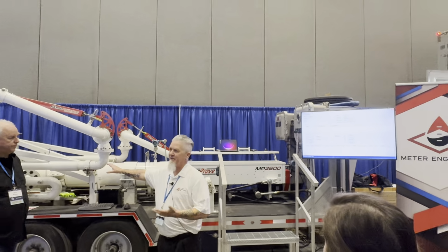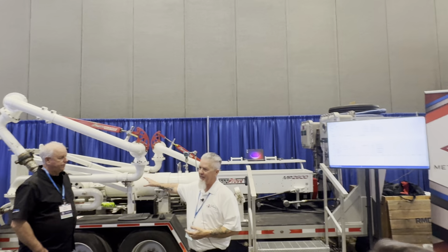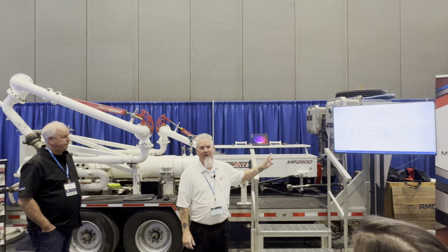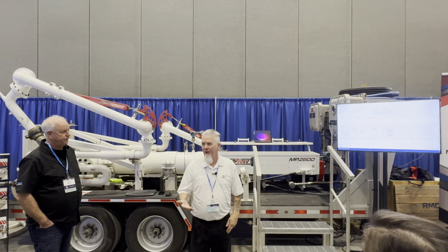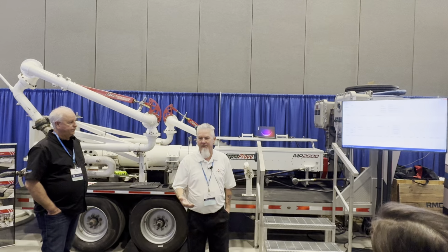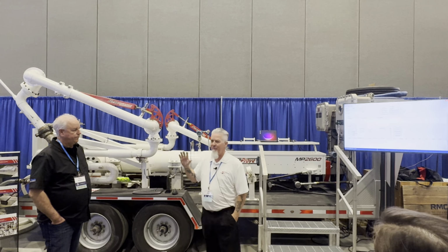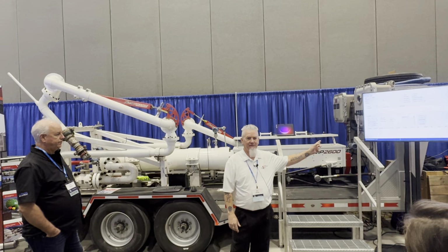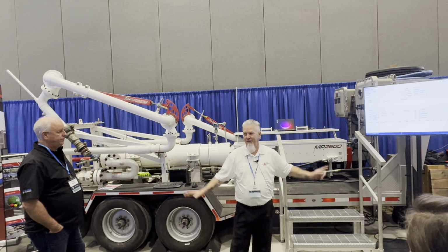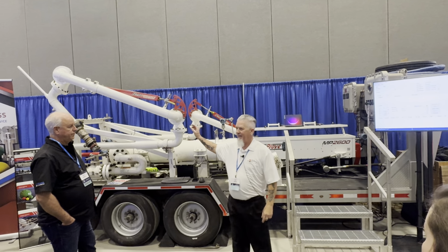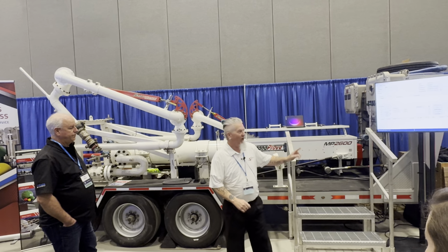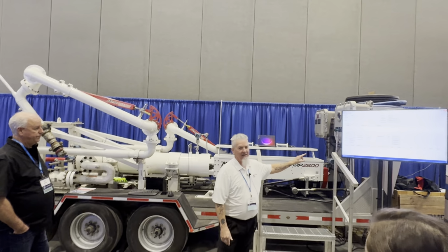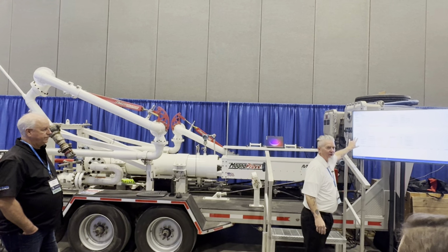It might say 60 degrees back there, but I have an offset in there, it might say 65, which it'll prove, but it'll be an incorrect meter factor. Okay? Everybody comes out and bumps that gauge back there, but nobody ever walks up and checks my prover. They shouldn't even worry about that gauge back there. They just need to put their thermal well in and walk up there to see whatever flow computer I have, what it's reading on the inside.